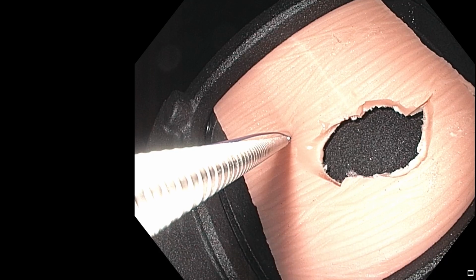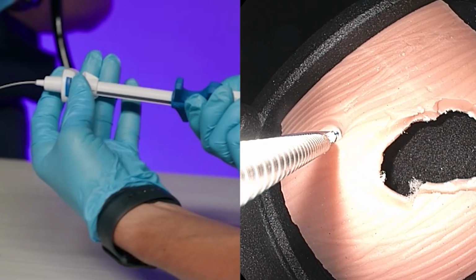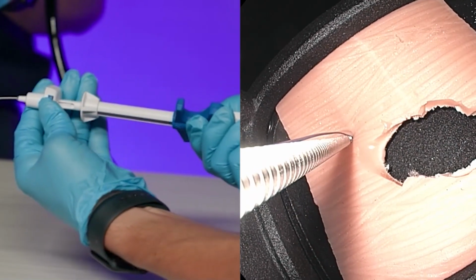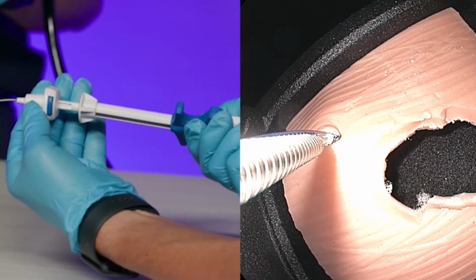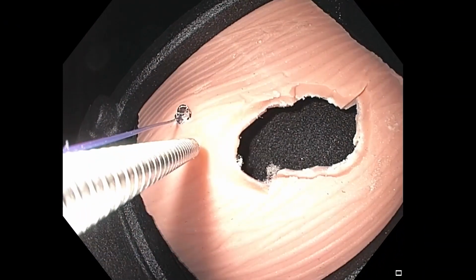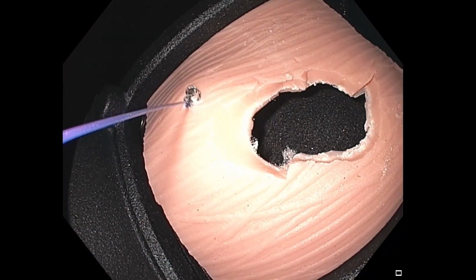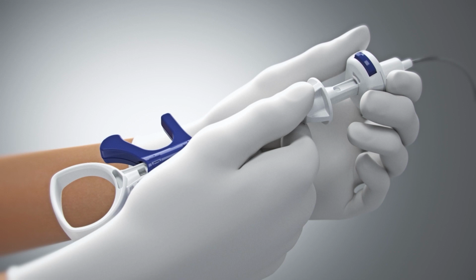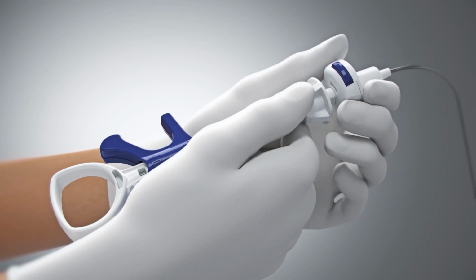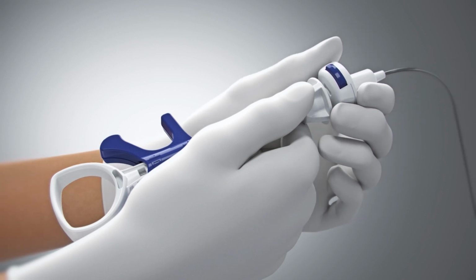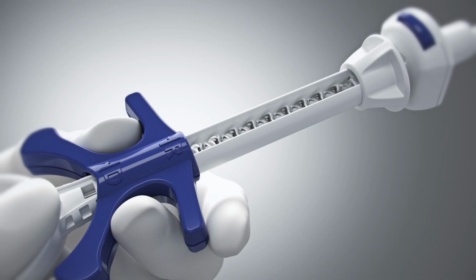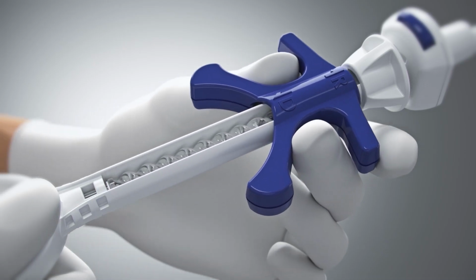To deploy the helix tack, ensure the handle slider is in the D position. Press and hold the blue release button while advancing the push catheter forward until the hard stop is reached. Remove the drive catheter from the scope. Reset the handle by sliding the push catheter back to the lock position until it clicks into place. Move the handle slider to the R position.